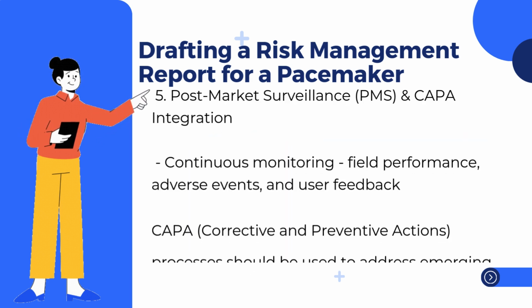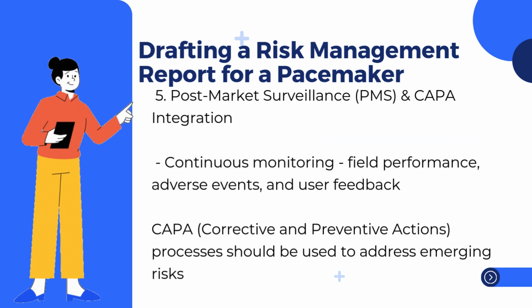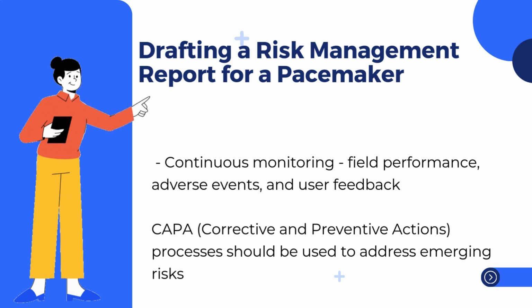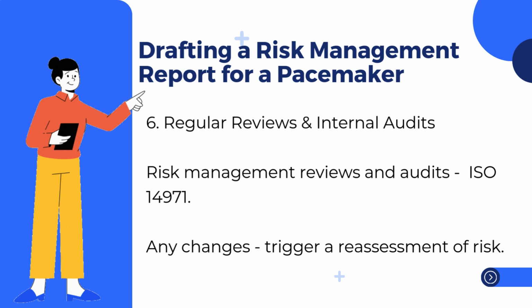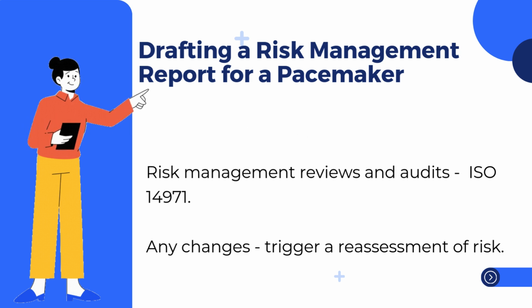5. Post-market surveillance, PMS, and CAPA integration. Continuous monitoring of field performance, adverse events, and user feedback ensures that new risks are identified. CAPA, corrective and preventive actions, processes should be used to address emerging risks proactively. 6. Regular reviews and internal audits. Periodic risk management reviews and audits ensure alignment with ISO 14971. Any changes in regulations or product modifications should trigger a reassessment of risk.